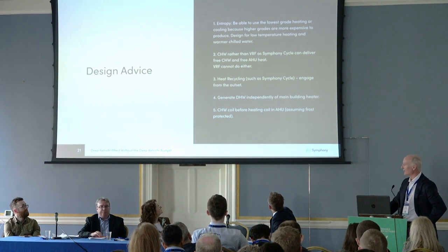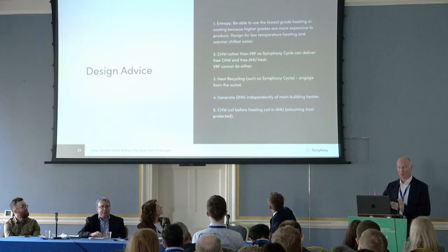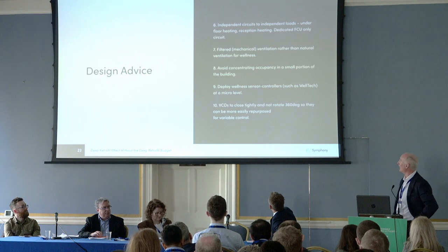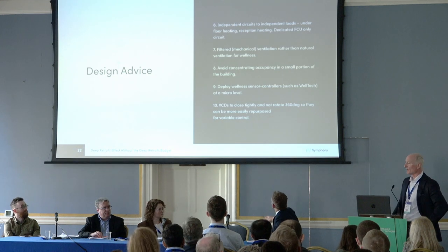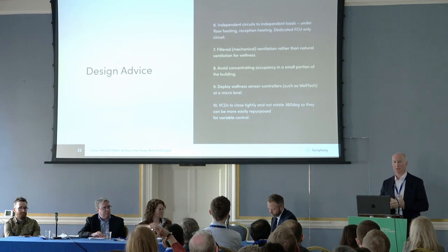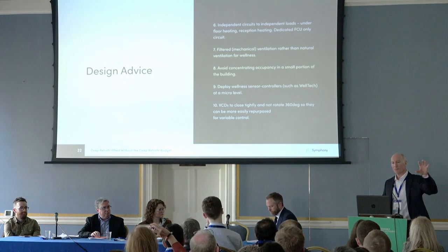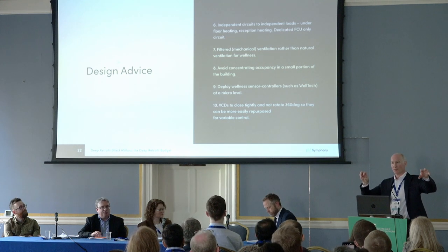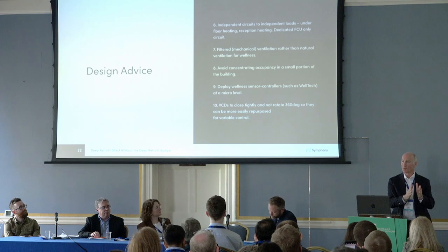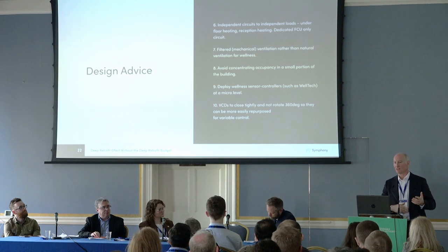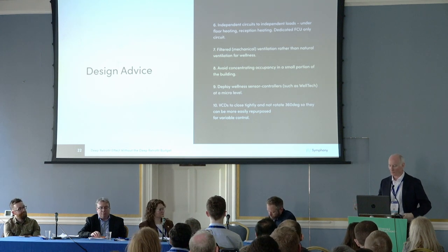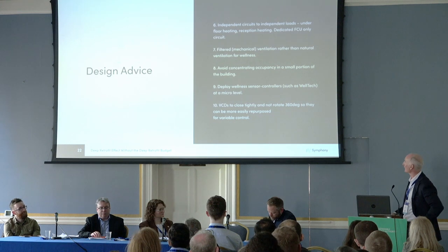Point number five, again with the heat recycling, it's best to have your chilled water coil before your heating coil. Number six, we see this time and time again, even in great buildings, where you've got different zone or load types and one heating circuit going to them, and you end up over-serving an area that doesn't need it. Get them onto independent circuits.